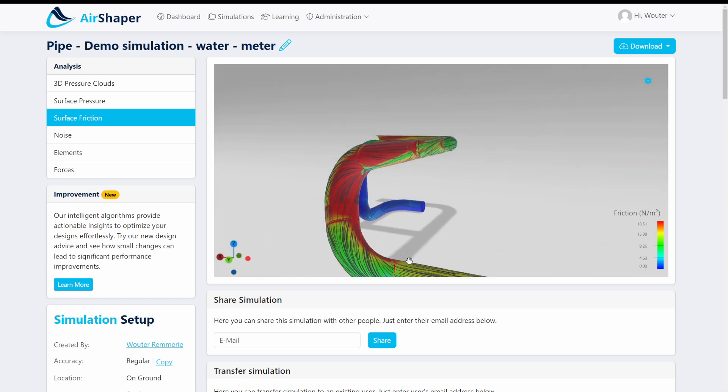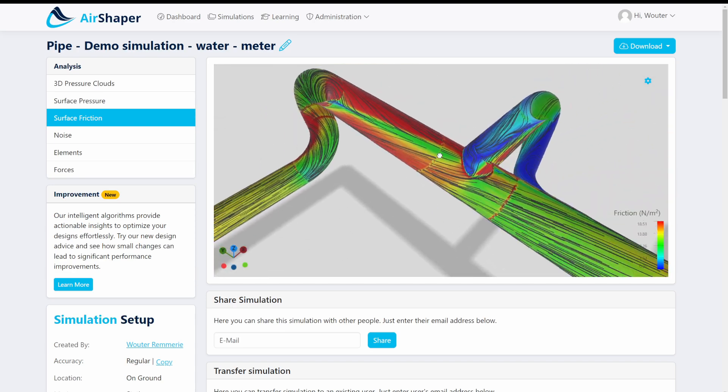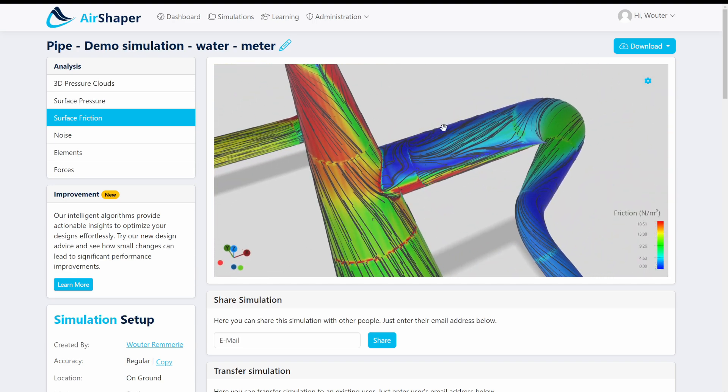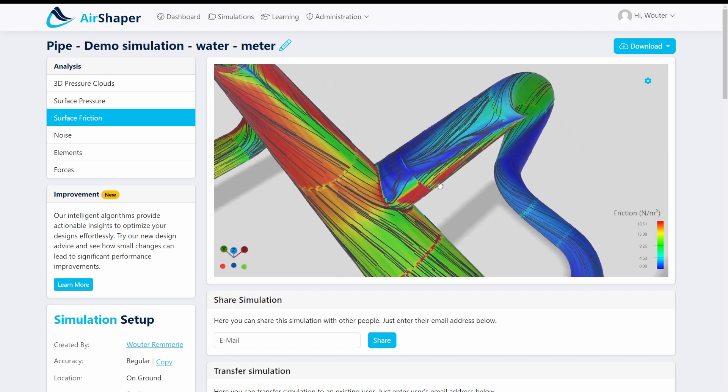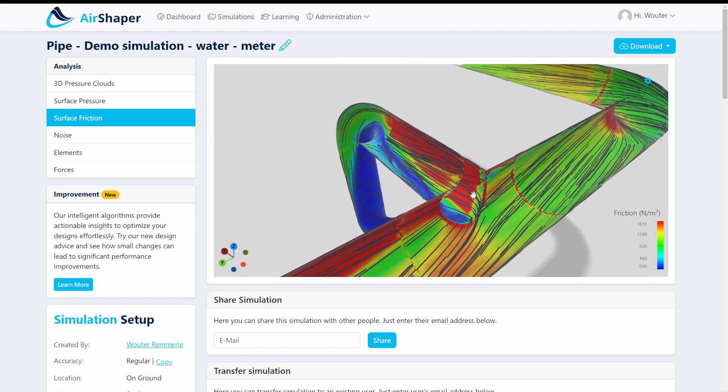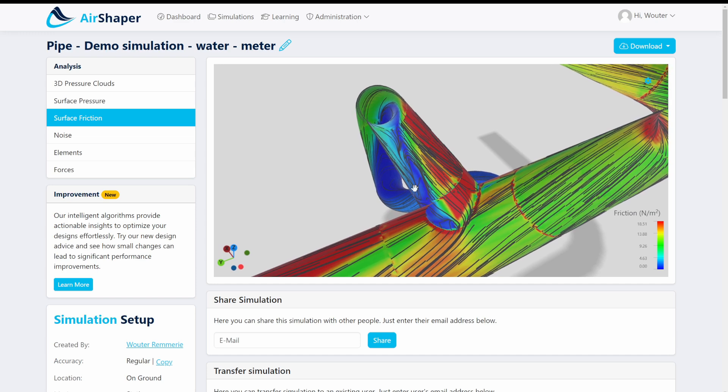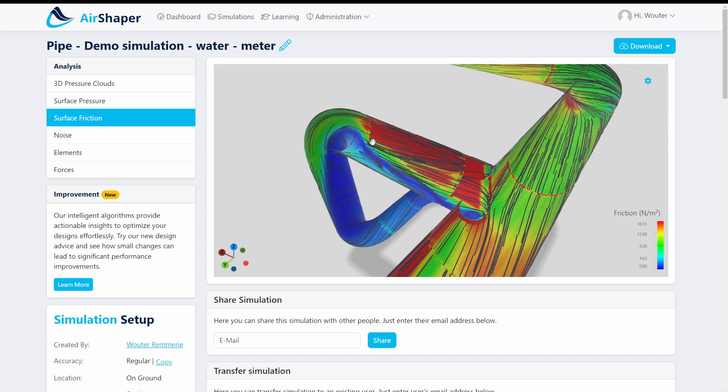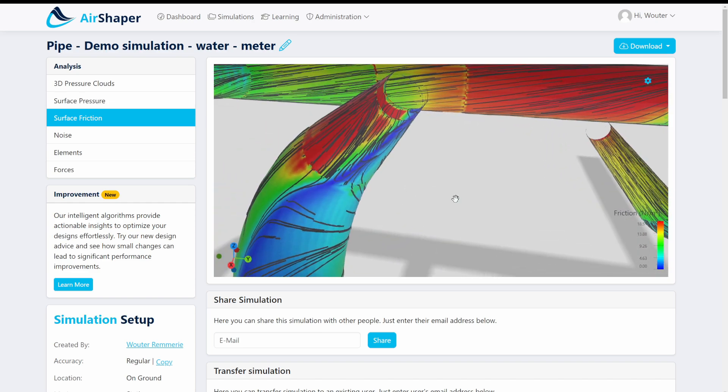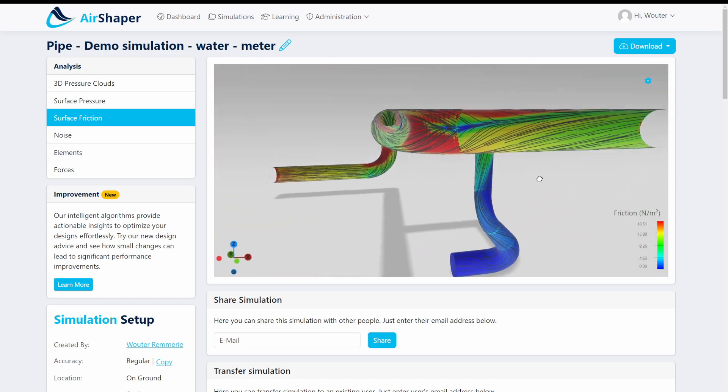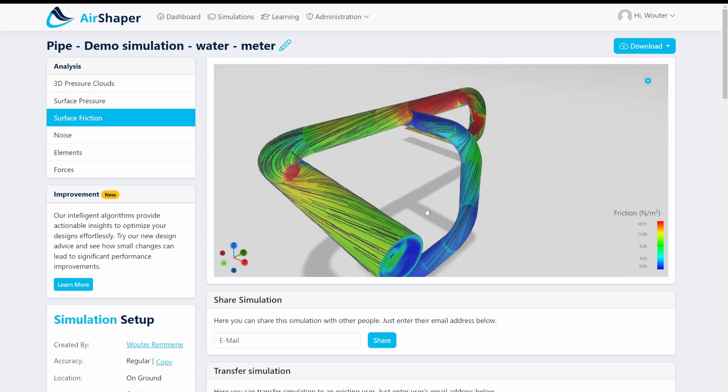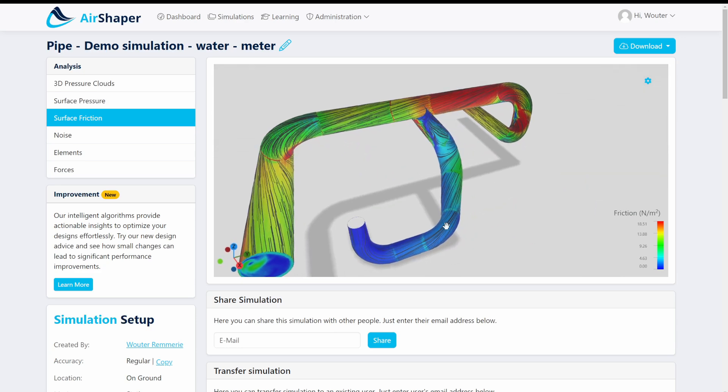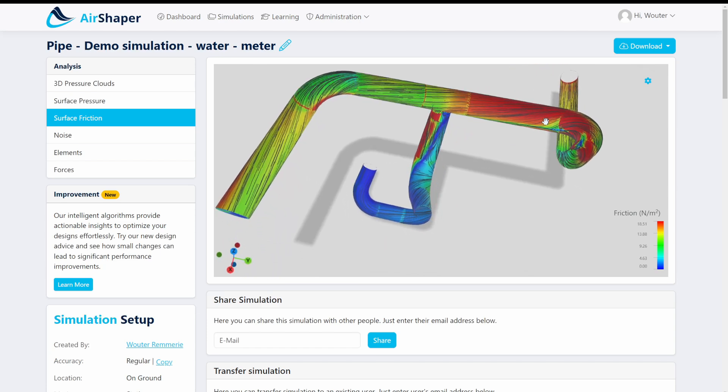You can actually really see this swirl of the flow so as you can imagine if you have to take two bends the flow actually rotates. In this case we have fully separated water flow on this side of the pipe and on this side we have attached flow because the water actually hits the surface and gets pushed against this side. You can see that this flow separation actually travels all the way down to most of the rest of the pipe here so it's very difficult for flow to reattach. Plus you do have a lower flow velocity overall because the majority of the flow is actually pushed through this part of the pipe network.